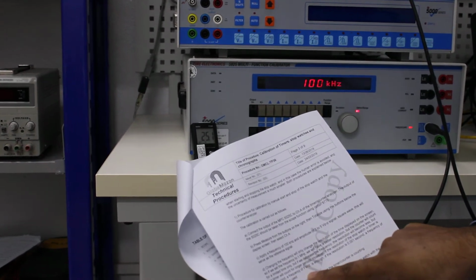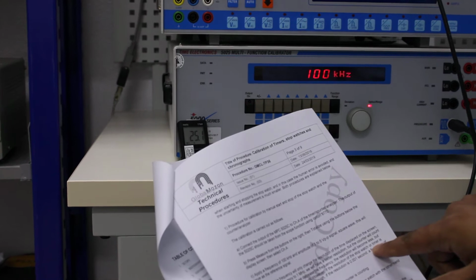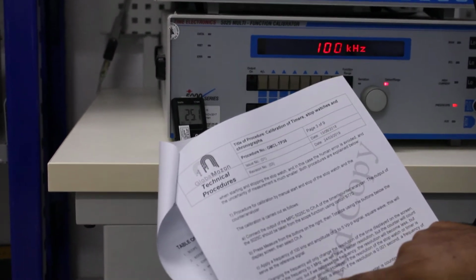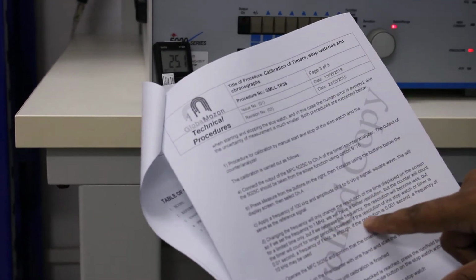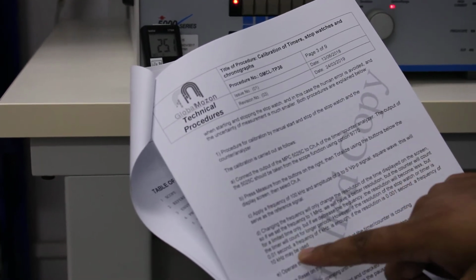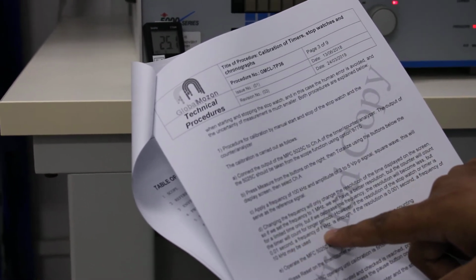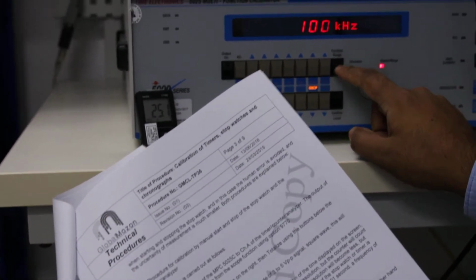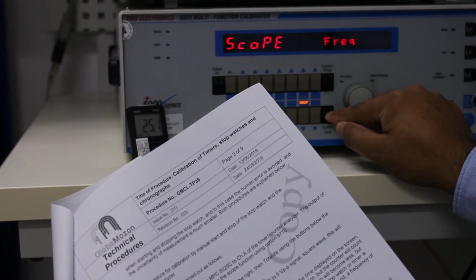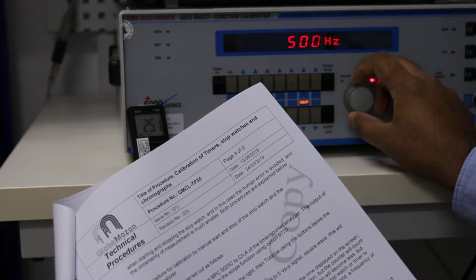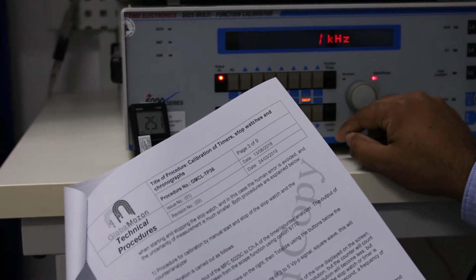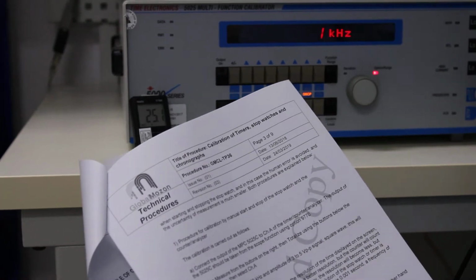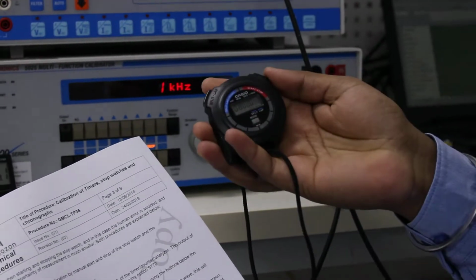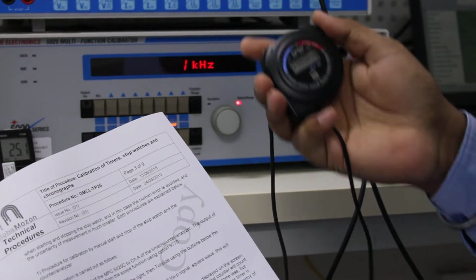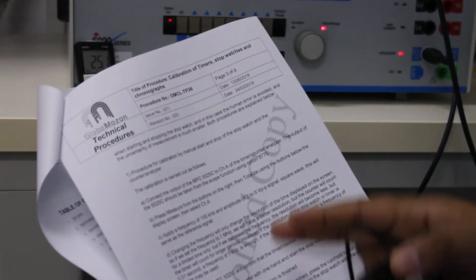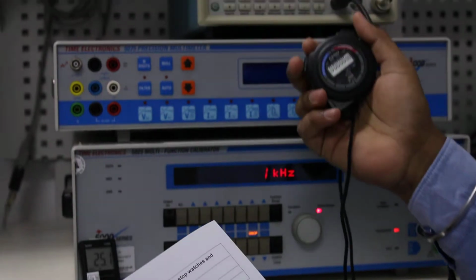This one has 1 kilohertz written here, but the timer will count for a longer period. However, the resolution of the stopwatch or timer is 0.01 second and the frequency is 1 kilohertz. So we will set our frequency to 1 kilohertz. We have set 1 kilohertz here. And now because our resolution is 0.01 second, we will start this calibration by pressing this function, and the start value comes here.